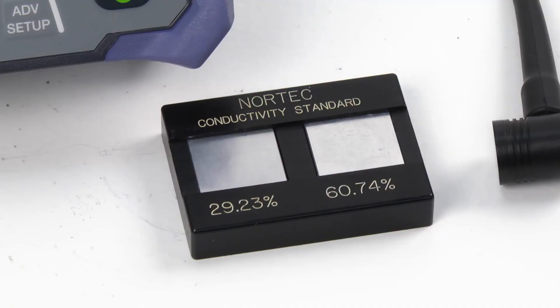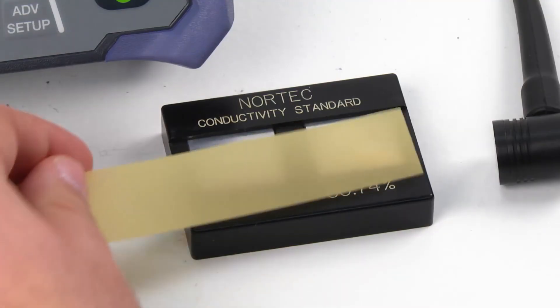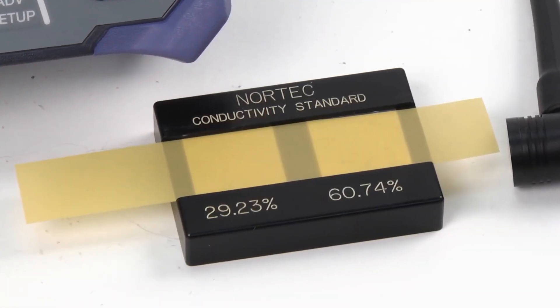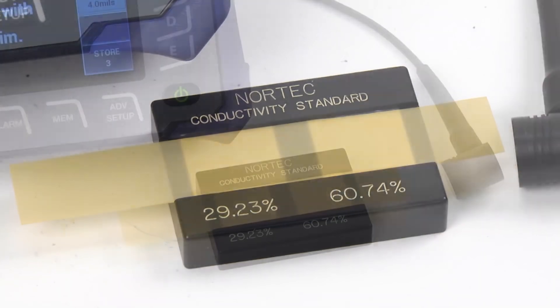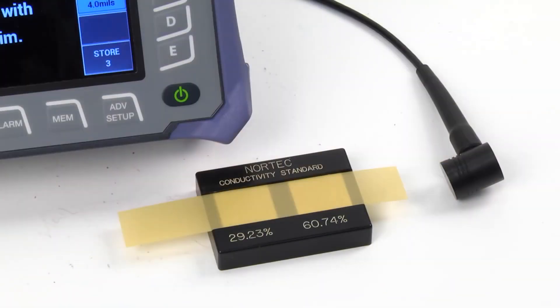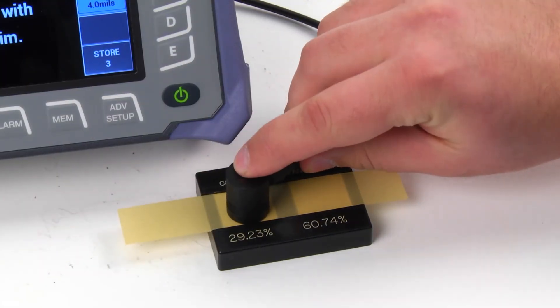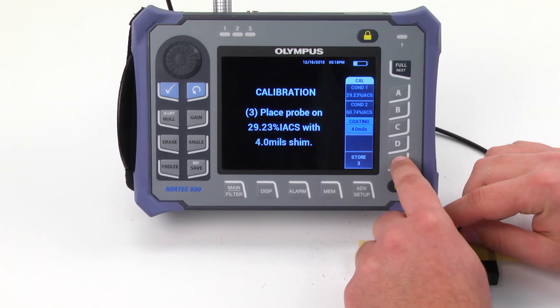Place a 4 mils shim on the standard. We are using a 4 mils shim to simulate a coating. Place the probe on the standard, starting with the left-hand side, and press E to store the reading.